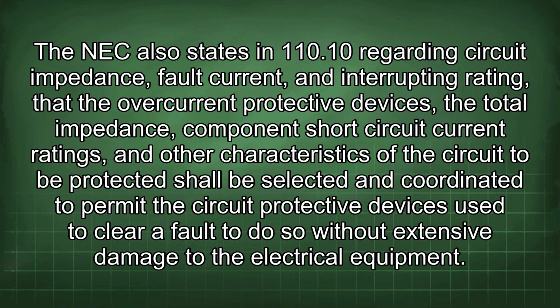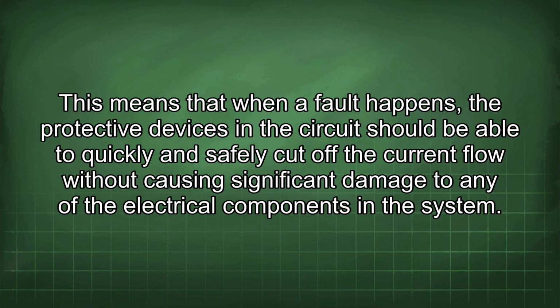The NEC also states in 110.10 regarding circuit impedance, fault current, and interrupting rating that the overcurrent protective devices, the total impedance, component short circuit current ratings, and other characteristics of the circuit to be protected shall be selected and coordinated to permit the circuit protective devices used to clear a fault to do so without extensive damage to the electrical equipment. This means that when a fault happens, the protective devices in the circuit should be able to quickly and safely cut off the current flow without causing significant damage to any of the electrical components in the system.